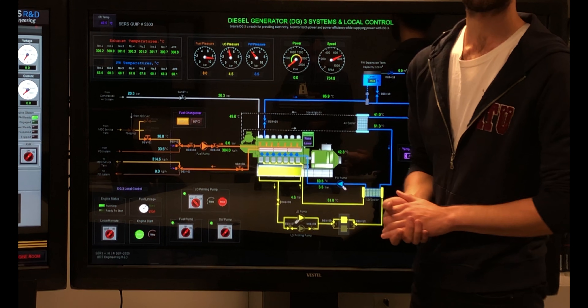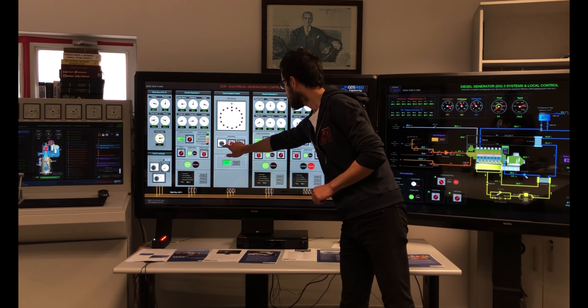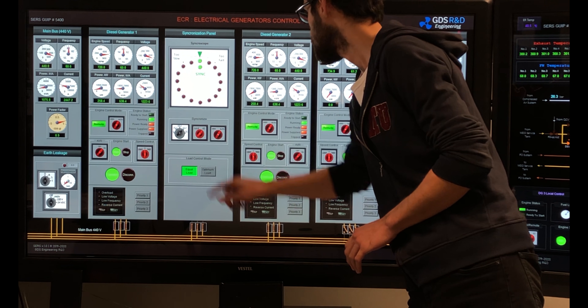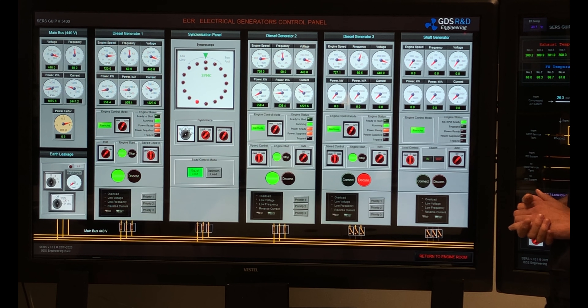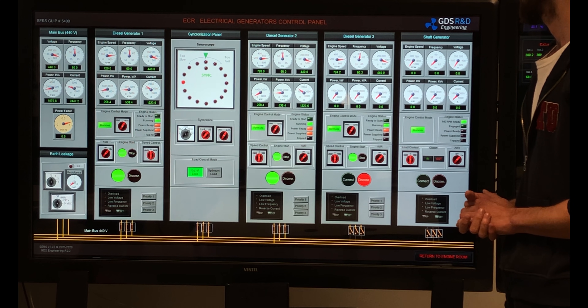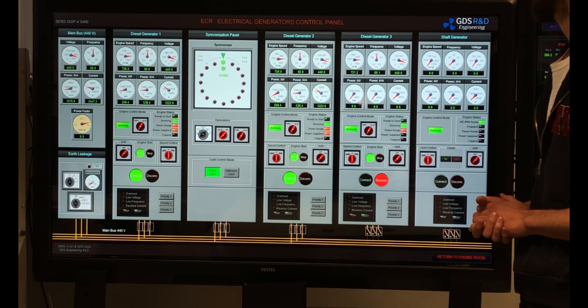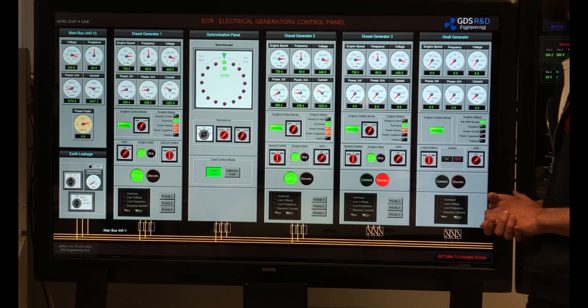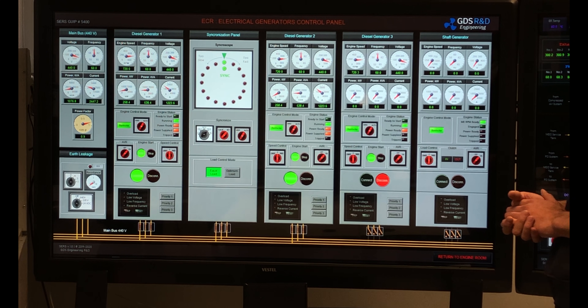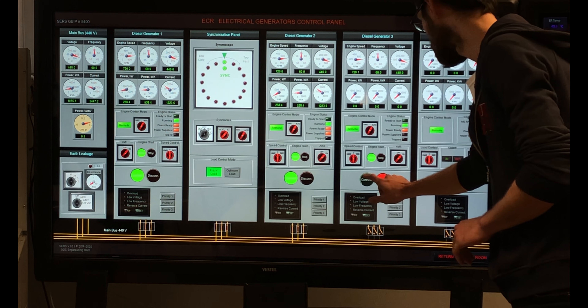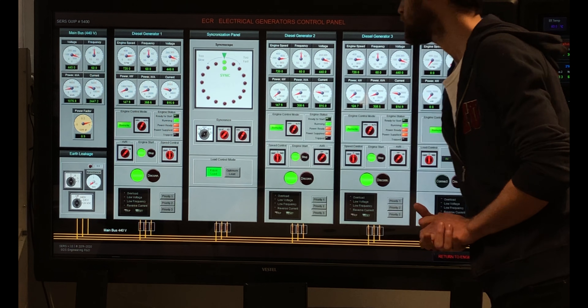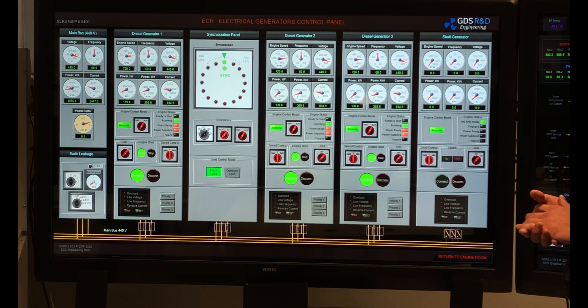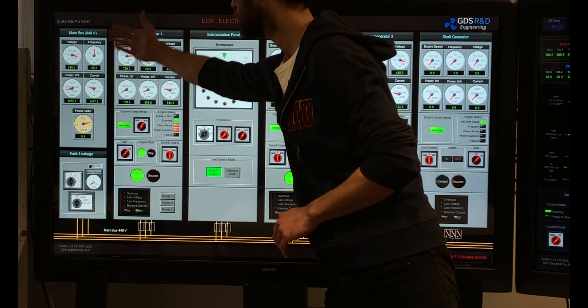I will synchronize it from the engine control room upstairs. In my synchroscope screen, I will switch to diesel generator 3. I can see that the diesel generator is running a little fast — the frequency shows 60.6, 60.5 Hz. I will wait for it to settle at 60 Hz. Once it looks good, I will connect diesel generator 3 to the bus bar. My generator operation mode is in equal load, so all three generators share the load equally, as I can observe on the panel on the left side of the screen.